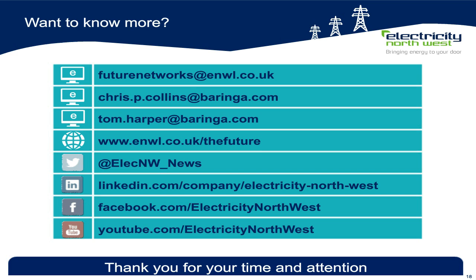Okay, we had a question of what type of loads are you targeting in CLASS? In the original project, we trialled CLASS on many types of loads: domestic, industrial, commercial, and a mixture. And we found we actually got a response on all load types. So CLASS will be rolled out at all primary types, regardless of what the actual load type is. The only slight difference is you get a difference in response. We did find you get a greater response for domestic loads as opposed to a mixed type or industrial.